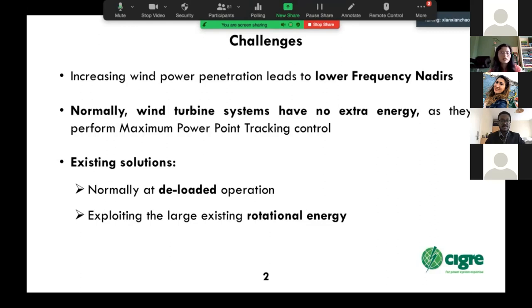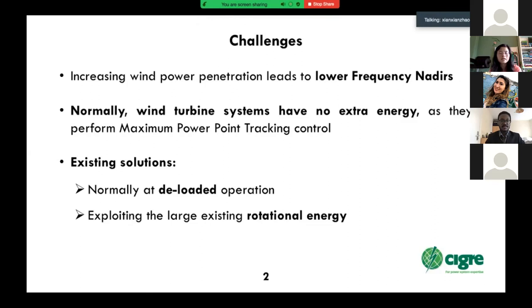To address this problem, in fact, we can use variable speed wind turbine systems. However, the challenge is that normally wind turbine systems have no extra energy as they perform maximum power point tracking control. There are two types of methods for wind turbine systems to provide faster frequency response. Type one, a wind turbine system is at deloaded operation at normal state. Type two, using the large existing rotational energy in a wind turbine system to provide a faster frequency response. This work is based on the second type because it will not cause financial and efficiency losses for wind farm owners.